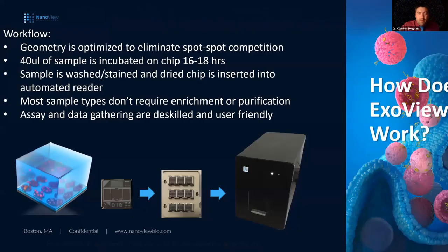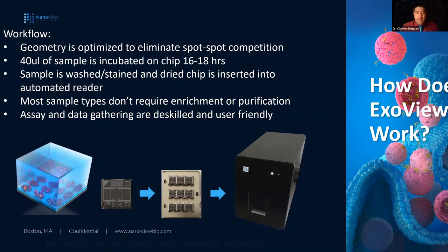The overarching workflow is the same whether you have an R100 or an R200. The chip geometry has been optimized to eliminate spot-to-spot competition, so spot replicates probe separate sets of particles. We use about 40 microliters during incubation — often diluted, so typically just one to two microliters of actual sample. The sample is then washed, stained, and read by the automated reader. Data gathering is completely automated, and many sample types don't require enrichment or purification.